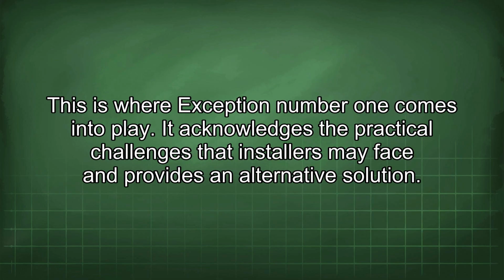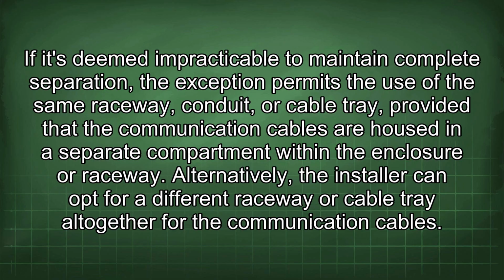This is where exception number 1 comes into play. It acknowledges the practical challenges that installers may face and provides an alternative solution. If it's deemed impracticable to maintain complete separation, the exception permits the use of the same raceway, conduit, or cable tray, provided that the communication cables are housed in a separate compartment within the enclosure or raceway. Alternatively, the installer can opt for a different raceway or cable tray altogether for the communication cables.